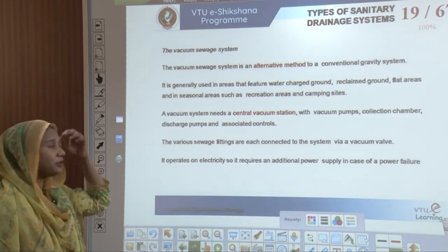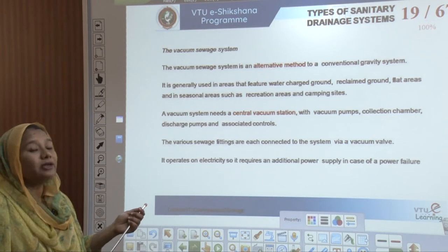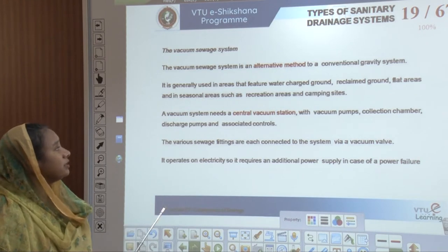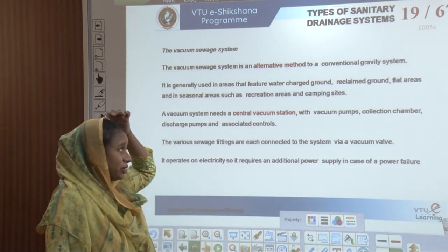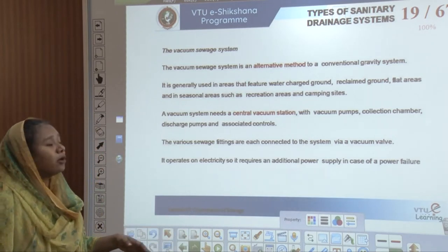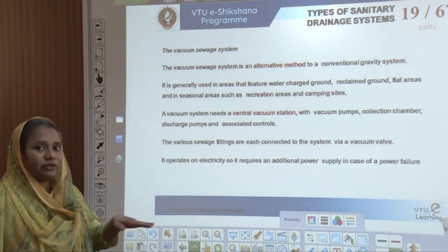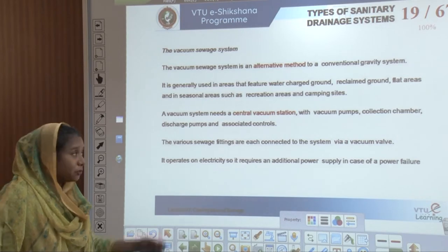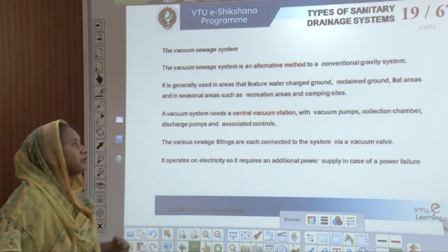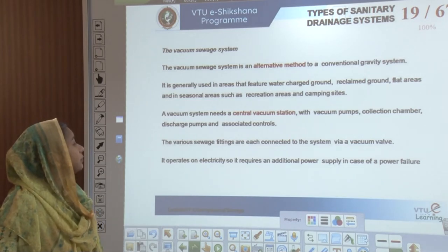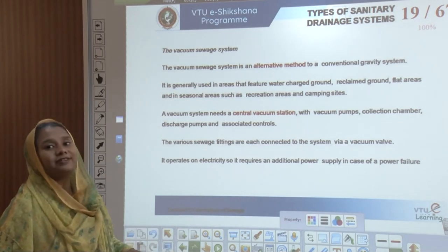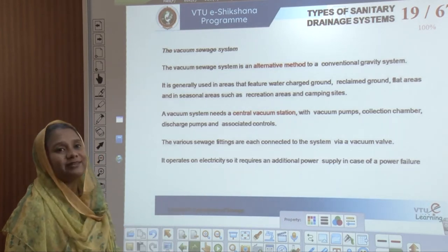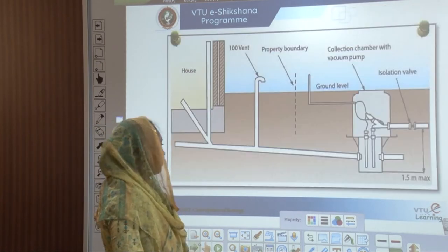This is also called the vacuum sewage system — an alternative method to the conventional gravity system. It is used in areas with water-charged ground, reclaimed ground, flat areas, or recreation areas such as camping sites. A central vacuum station is needed with vacuum pipes, vacuum pumps, collection chambers, discharge pumps, and associated controls. The fittings operate on electricity, so an additional power supply is required in case of power failure.